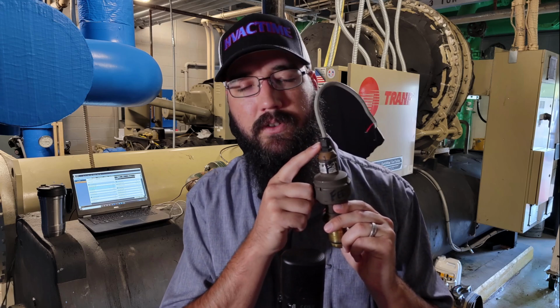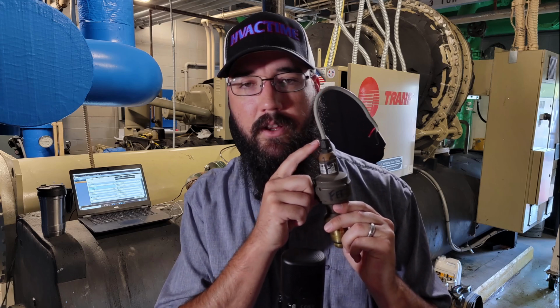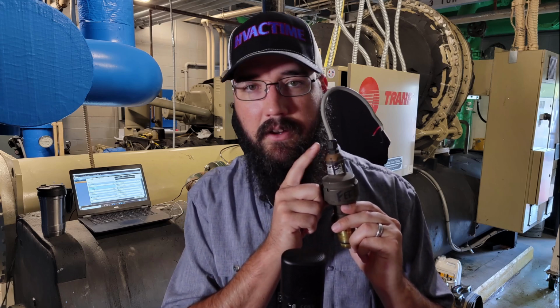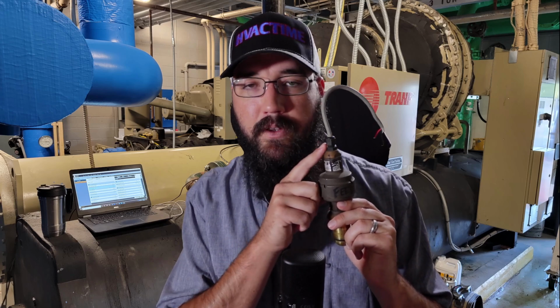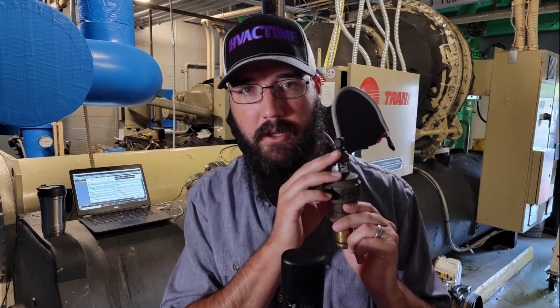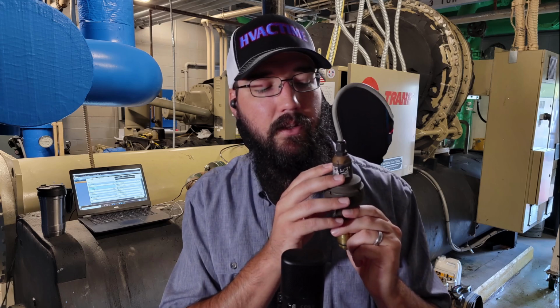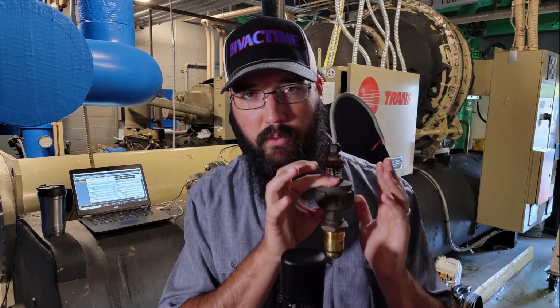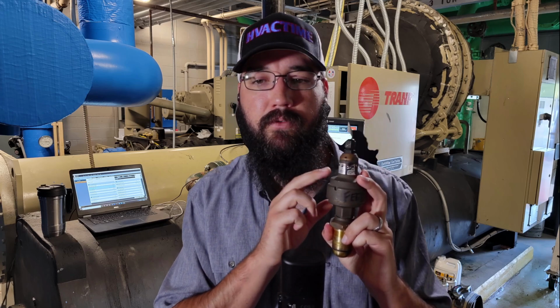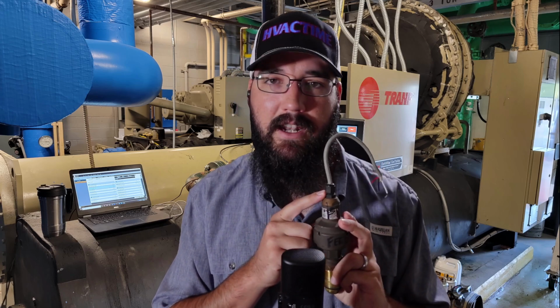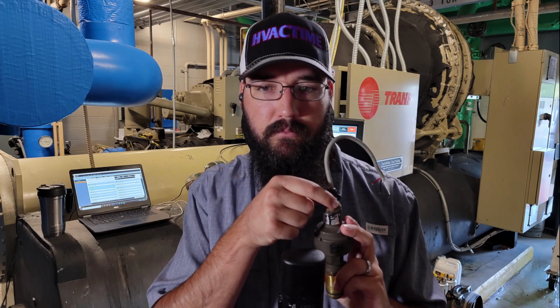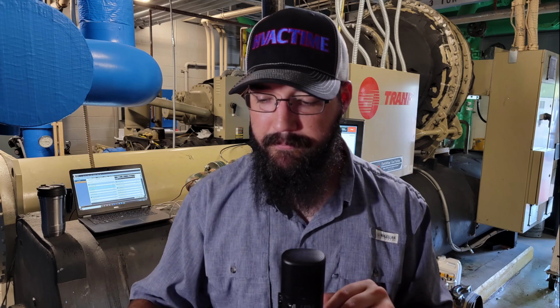Now, some of these, the newest ones, are using a removable plug here. I say removable as in it's got a plug instead of a hard cable. You cannot take this out. This is not serviceable. This whip is permanently a part of this valve body. So a lot of the newest ones have moved away from this style and have moved towards an interchangeable whip. I think that was an improvement.